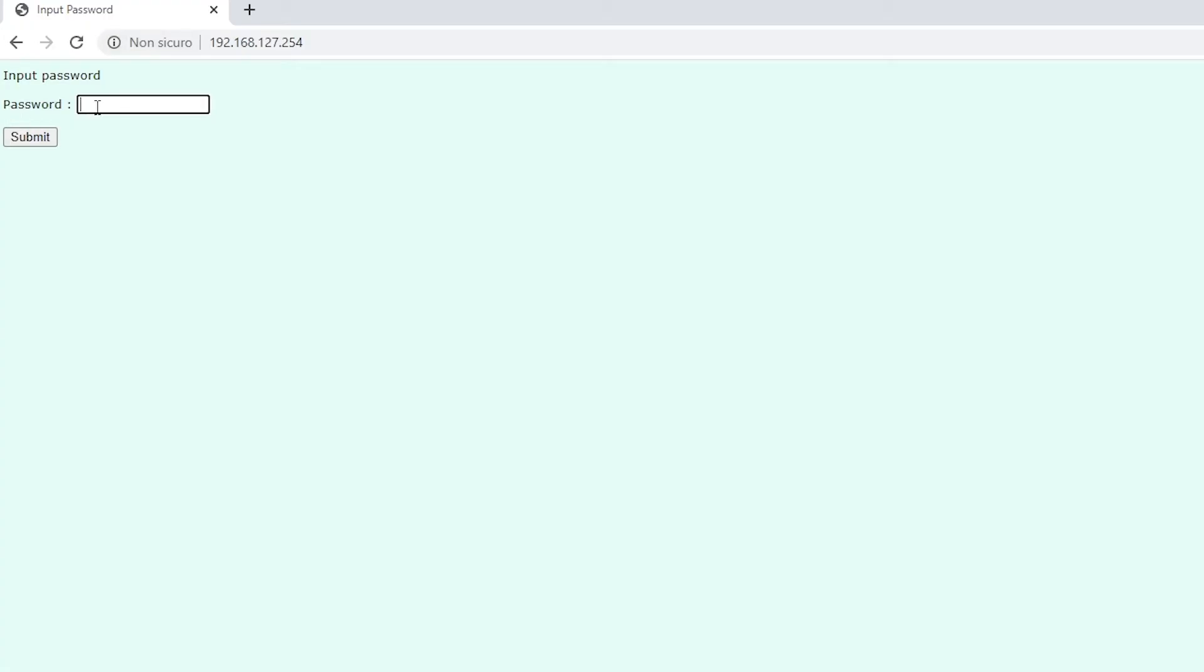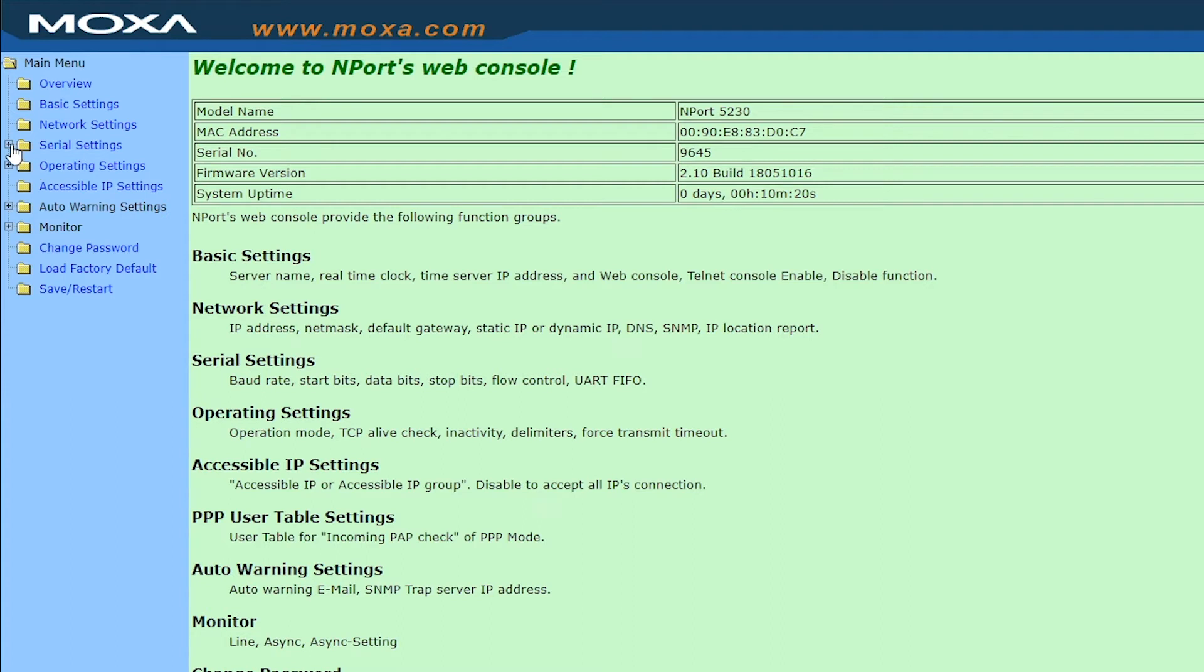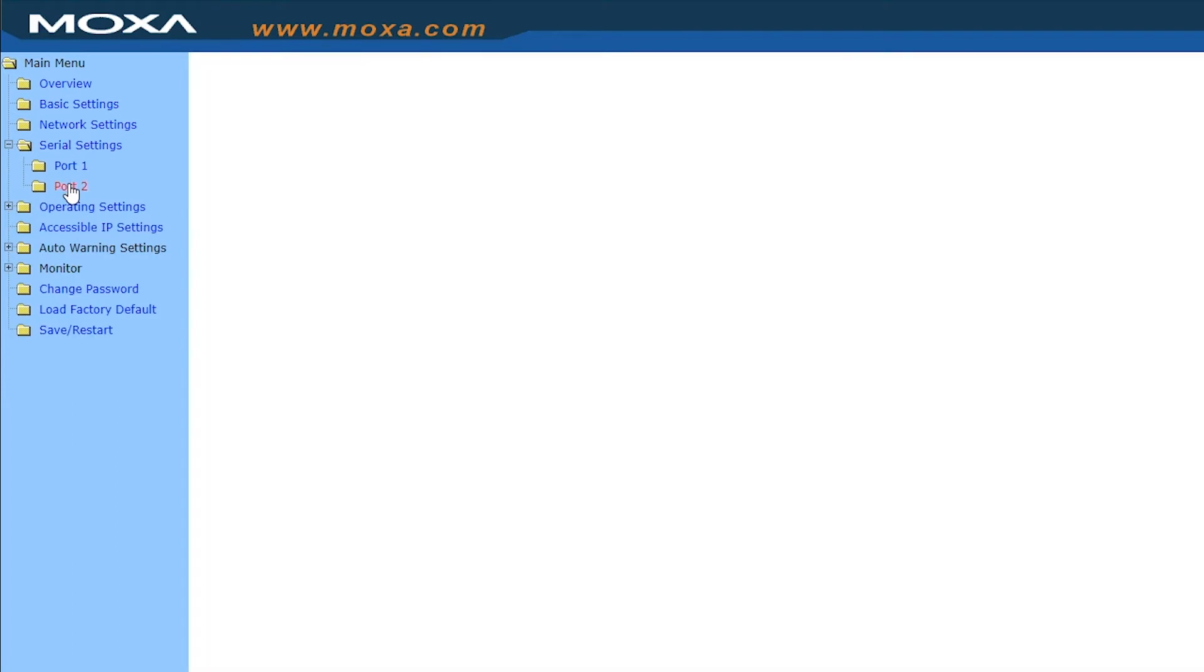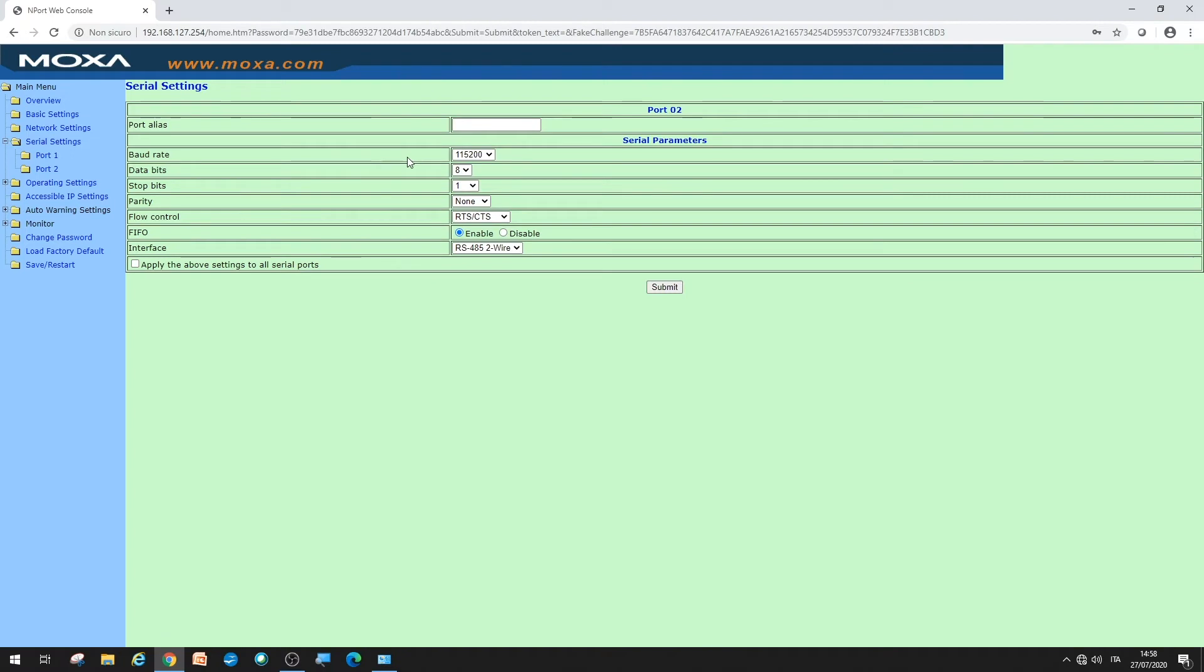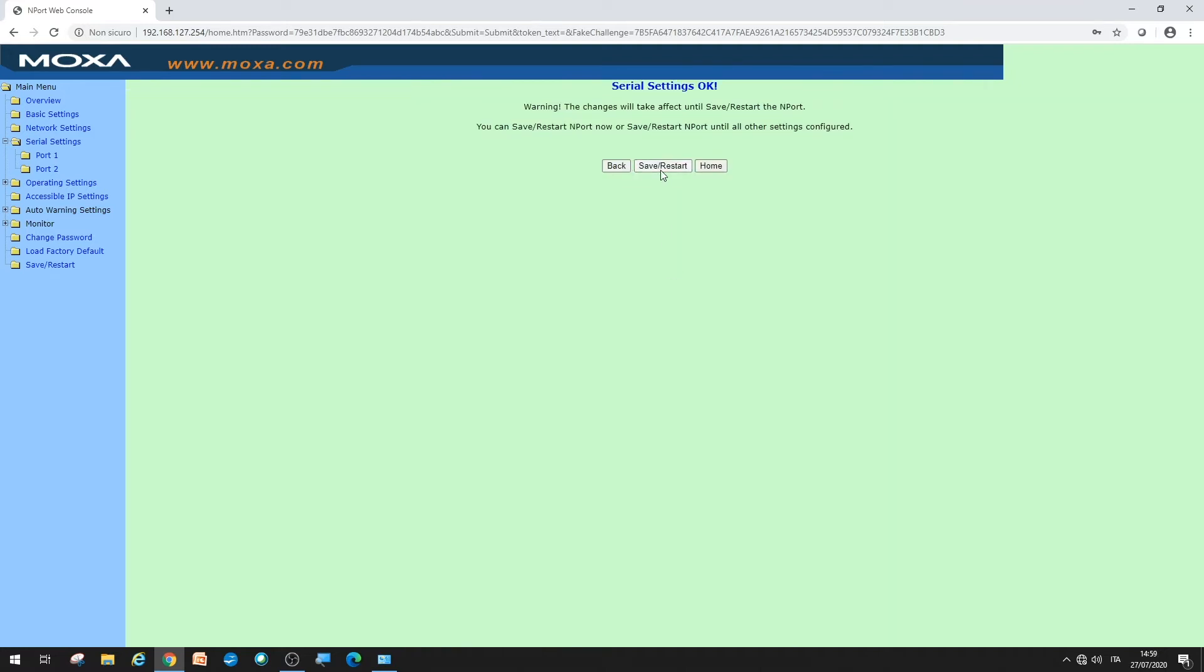The default password is Moxa. In serial settings for port number 2, set the baud rate to 38400 and the flow control to none. For the other parameters, leave the defaults. Press submit to save and restart.